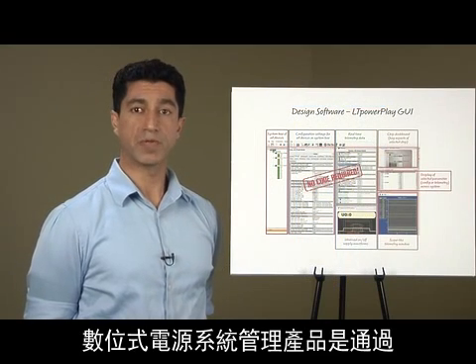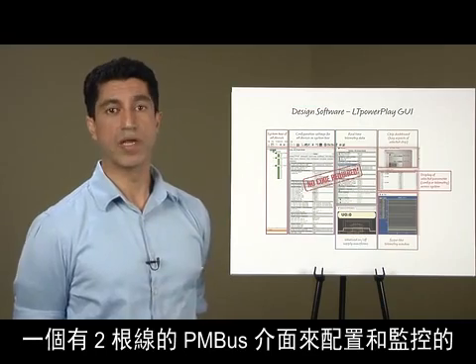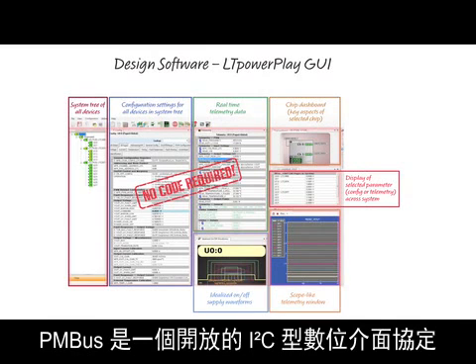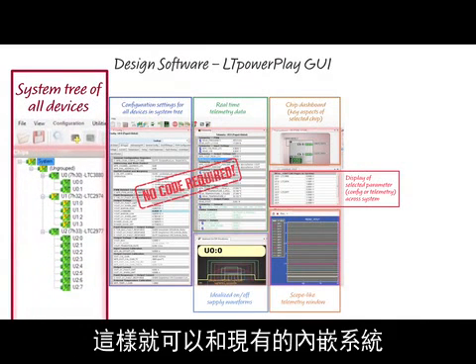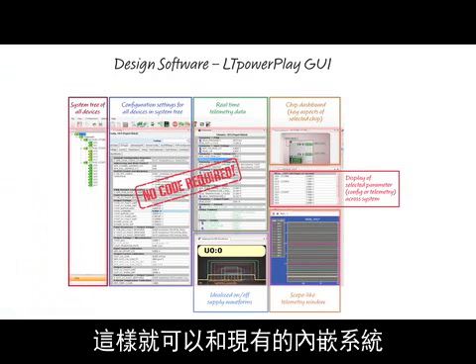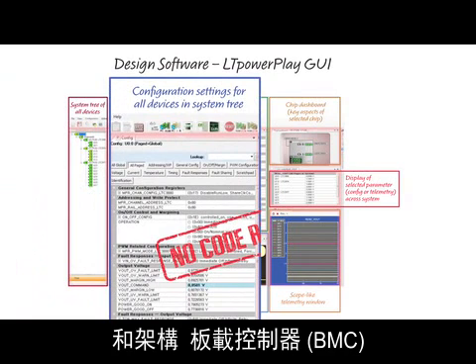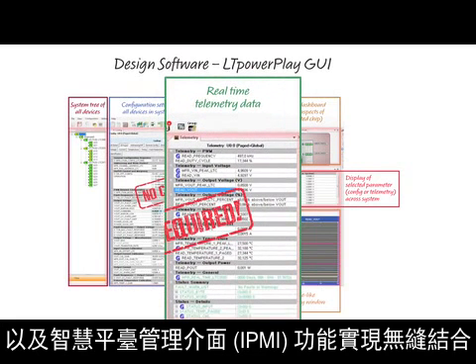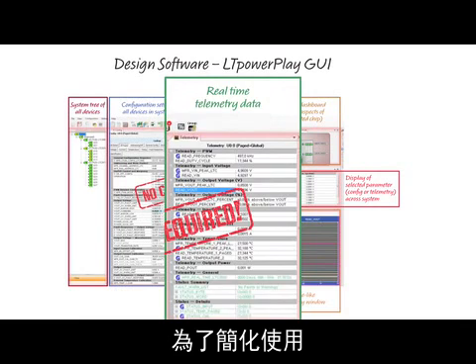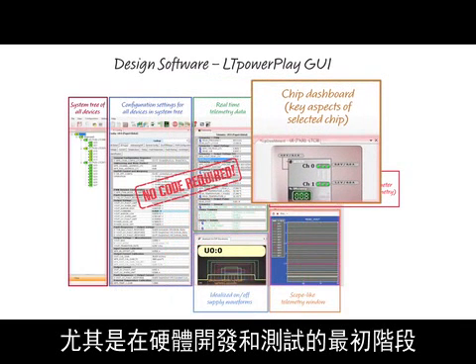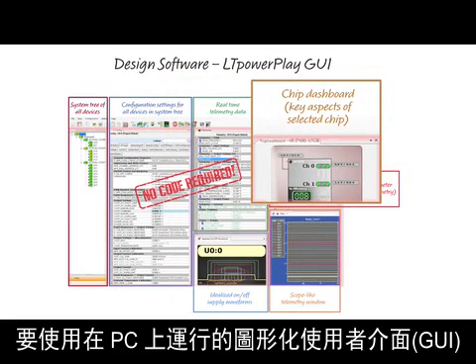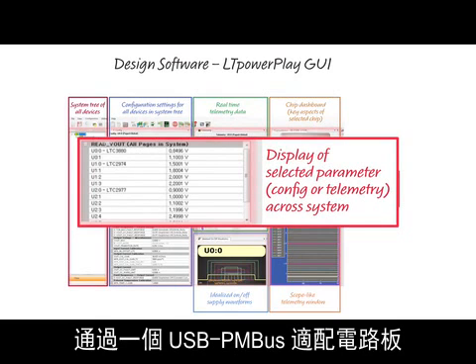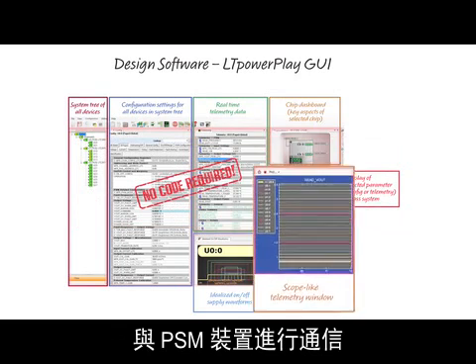Digital power system management products are configured and monitored via a two-wire PMBus interface, an open I2C-based digital interface protocol. This enables seamless integration with existing embedded systems and architectures, baseboard management controllers, BMCs, and intelligent platform management interface, IPMI, functions. For simplicity and ease of use, especially at the earliest stages of hardware development and testing, a GUI running on a PC is used to communicate with a PSM device through a USB to PMBus adapter board.